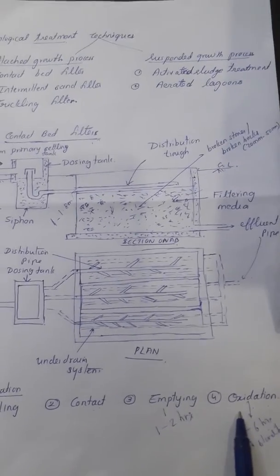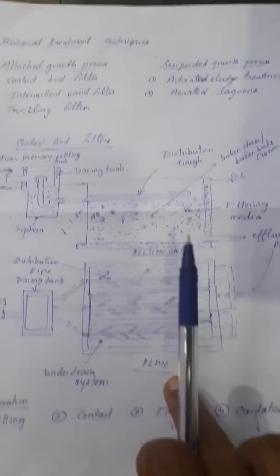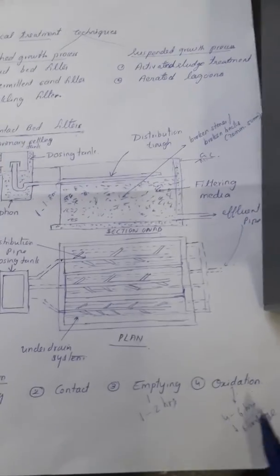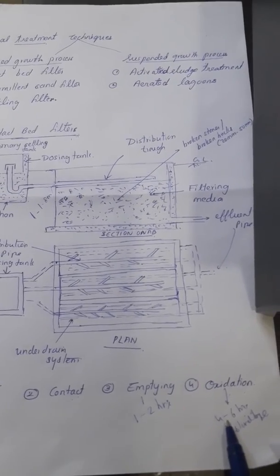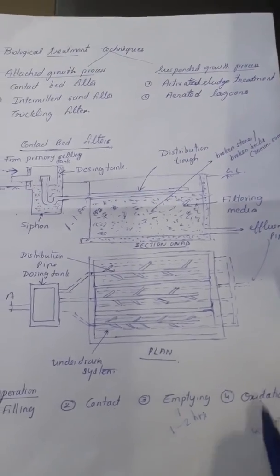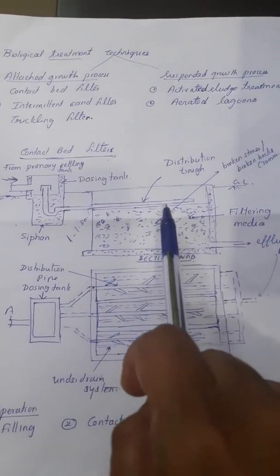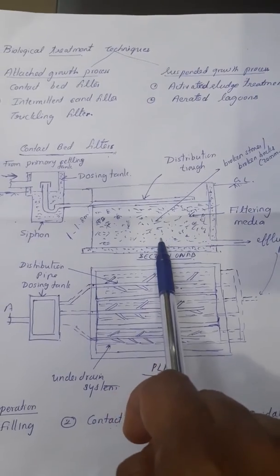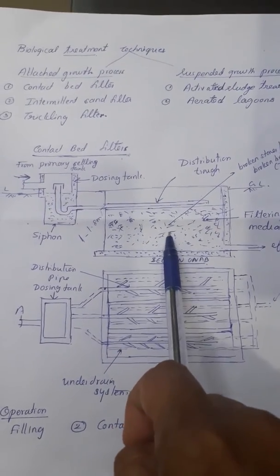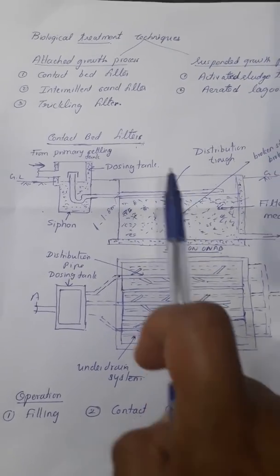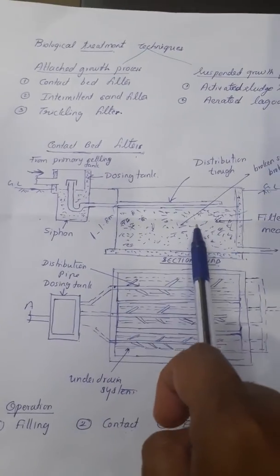The fourth operation is oxidation. In this oxidation process, the contact bed is allowed to stand empty for 4 to 6 hours. During this period of rest, atmospheric air enters into the void space of the contact media, thus supplying oxygen to the aerobic bacteria, which results in the oxidation of organic matter present in the film. This is the working of this contact bed filter.